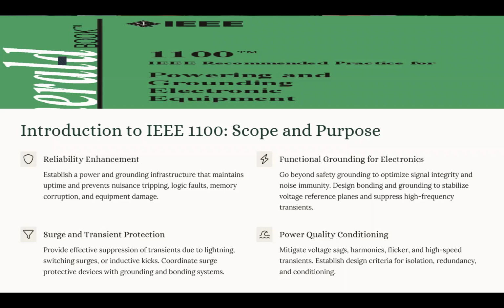Now, there are some key objectives in IEEE 1100. One would be reliability enhancement, where the goal is to keep sensitive electronic systems running continuously without any unexpected shutdowns, data loss, or malfunction. How we do that is through designing the power distribution and the grounding system so we could avoid the tripping of the breakers. Another approach for this goal is preventing logic faults. Okay, when we talk about the microprocessor, it could misread some data due to ground noise. We also want to minimize memory corruption in digital systems, which is normally caused by voltage transients or a ground bounce.